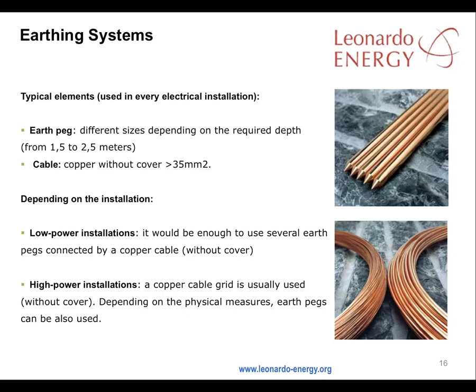Earthing pegs connected by uncovered copper cable should be sufficient for lower power installations. High power installations usually use an uncovered copper cable grid, though earthing pegs can also be used in certain situations. A typical earthing system for your PV facility will require 35mm uncovered copper cable together with earthing pegs of different sizes depending on the required depth, normally between 1.5 and 2.5 meters.